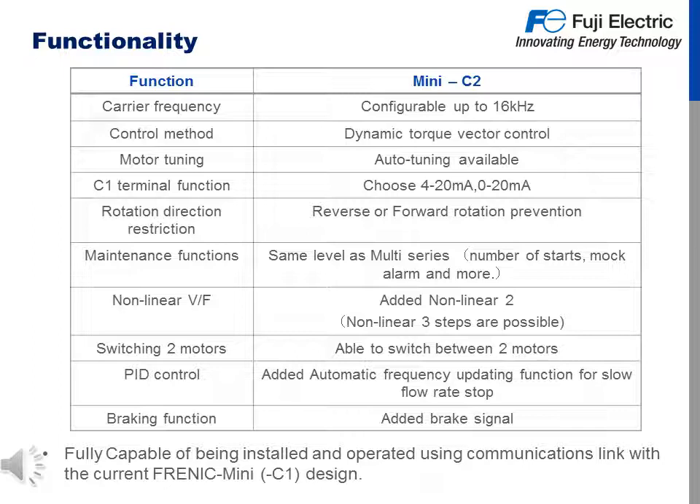Additional functionality and features added to the Mini C2 include a carrier frequency now configurable up to 16 kHz, dynamic torque vector control for speed and torque accuracy, and the ability to auto-tune your motor. The C1 terminal function can be altered between 4 to 20 mA or 0 to 20 mA. You can restrict either forward or reverse rotation. Maintenance function has been upgraded to the same level as multi, featuring number of start-ups and mock alarms. Added non-linear volts per hertz pattern number 2, where 3-step non-linear adjustment is possible. You can set up and program for two different motors and applications. PID control now includes automatic frequency updating function for slow flow rate stop, or PID sleep mode, and a braking function added as an output for conveyance-type machinery.